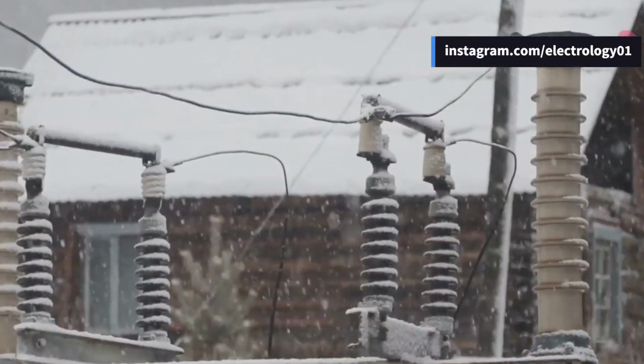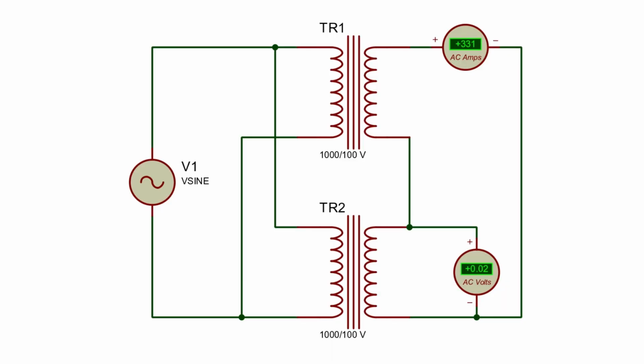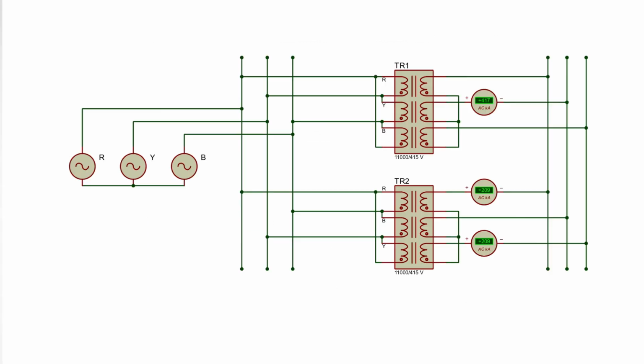Then we have polarity. All transformers operating in parallel should have the same polarity, or the instantaneous direction of induced EMF in the secondary. If two transformers have opposite instantaneous directions of induced secondary EMF when fed the same input power, they are said to have opposite polarity. If the directions are the same, they have the same polarity. If the polarities are not the same, a huge circulating current will flow in the transformers, but no load will be fed from them. Finally, there's the phase sequence.